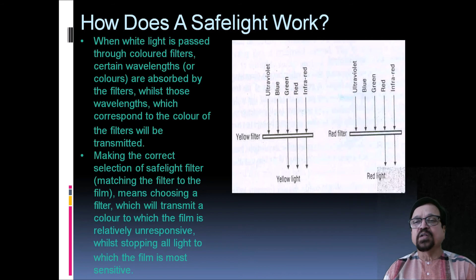Now, making the correct selection of the safe light: matching the filter to the film means choosing a filter which will transmit a color to which the film is relatively insensitive, while stopping all the light to which the film is sensitive. Now, spectral transmission graph. Manufacturers produce a graph for their safe lights called spectral transmission or filter transmission graphs. Their purpose is to indicate the part of the visible spectrum which will be transmitted by the filter, so that the radiographer can match the appropriate filter to the type of film he is using.